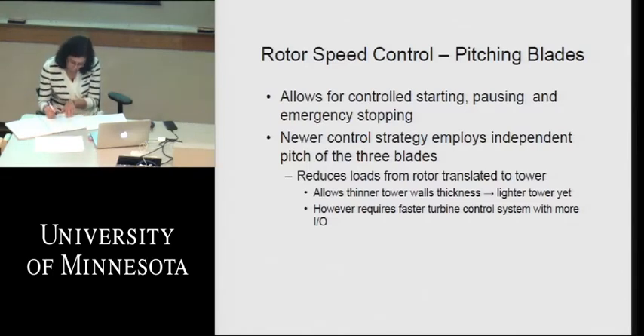But to do this, the control system within the turbine has to have a lot more inputs and outputs, a lot more I/O for strain gauges and accelerometers that we actually put in the blade to tell how the blade is reacting to this independent pitch. If you can imagine why we do this, take a blade at 12 o'clock, meaning the other 2 blades would be at 4 o'clock and 8 o'clock. The one at 12 o'clock would have the highest forces because it's sticking up highest into the wind.